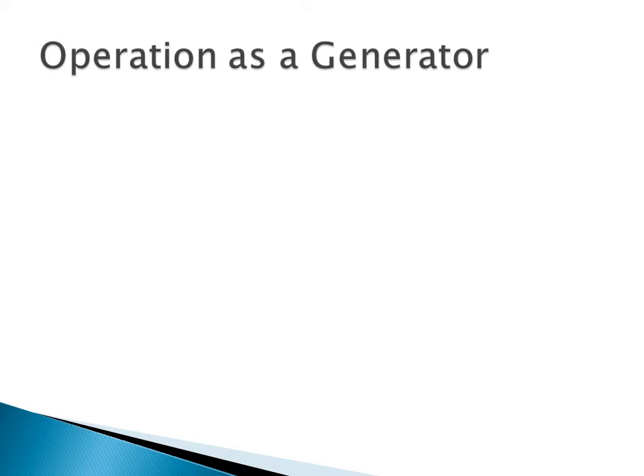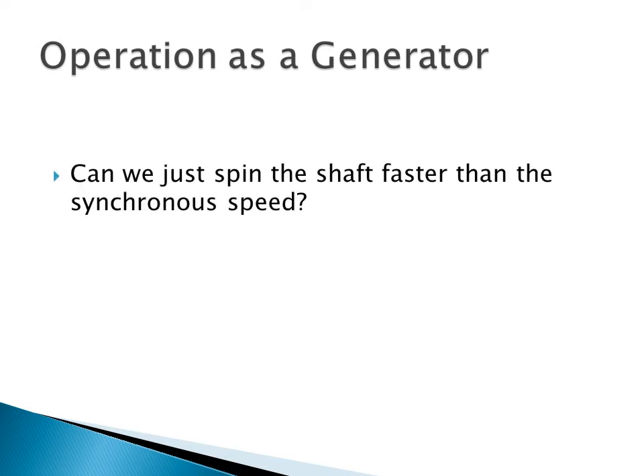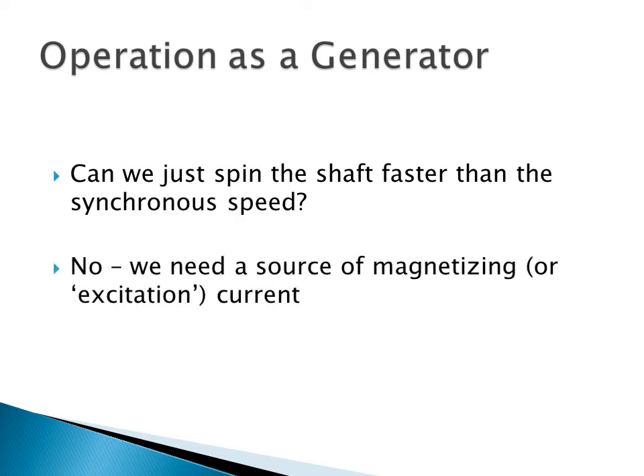Now, we may be wondering, can we just spin the motor at the required speed, 1890 RPM, and hope that it produces power? The answer is, well, no. We need to provide magnetizing current, and we can't do that if we're just spinning the motor. It needs a source. Since we don't have the grid, we're going to need to provide the current some other way.